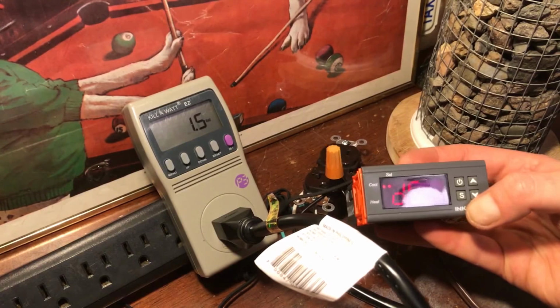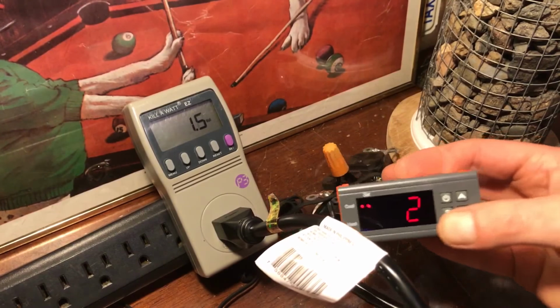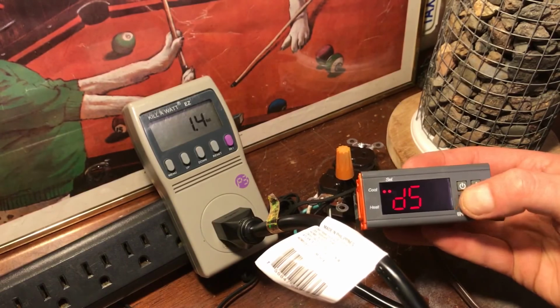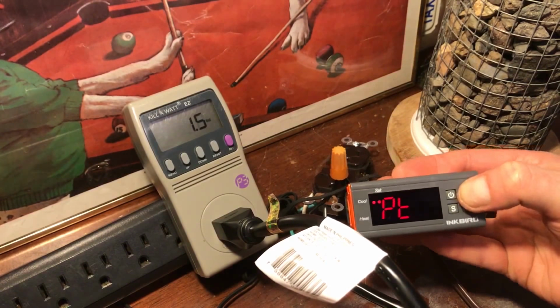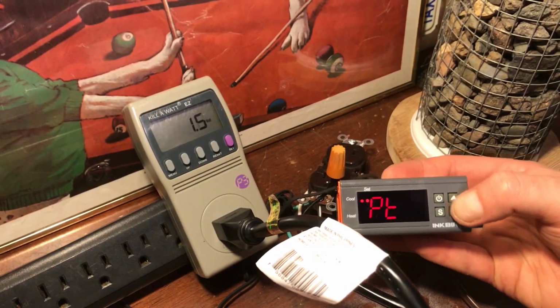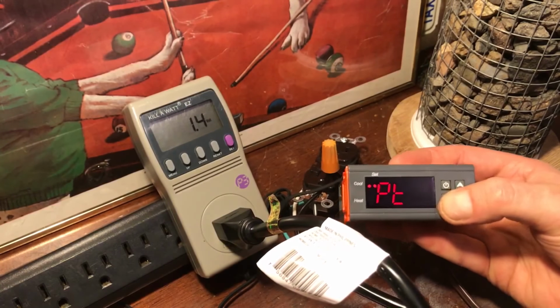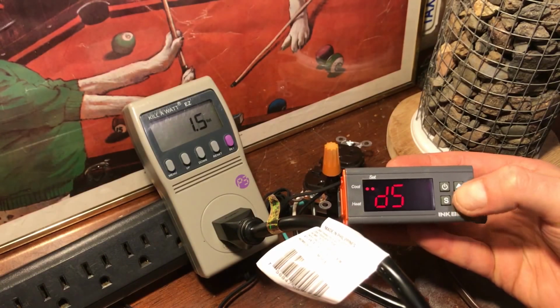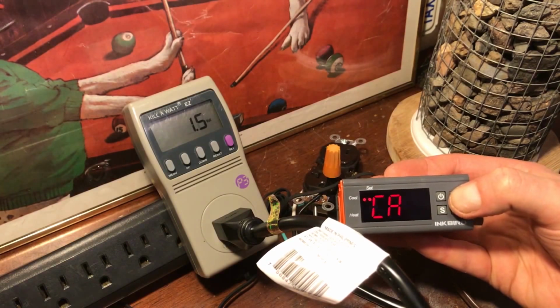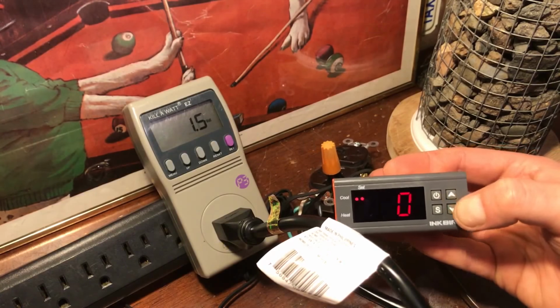Okay, so DS is the differential value. I want that at 2 degrees Fahrenheit. PT is the compressor delay, we'll have that at 0. And the calibration value, we'll keep it at 0 for now.